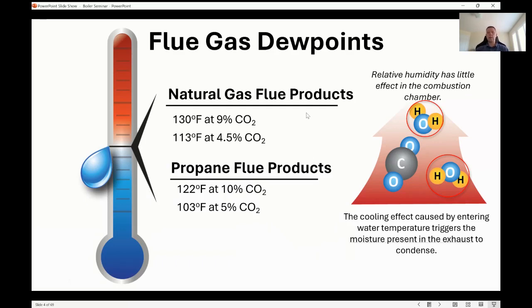A fan-assisted type product with natural gas will have a dew point of 130 degrees. That dew point of 130 degrees Fahrenheit is representative of your return water temperature. Most manuals will say 140 because 140 sometimes can mean 130 in the field. Anytime you operate above that number, whether it's a condensing boiler or not, you're in non-condensing mode. Anytime you operate below that number, you're going to be in condensing mode, and that water vapor is going to condense and turn to a liquid. As I said, it does vary depending on the fuel. If you're using LP, that number becomes 122 degrees, and that's at 10% CO2.